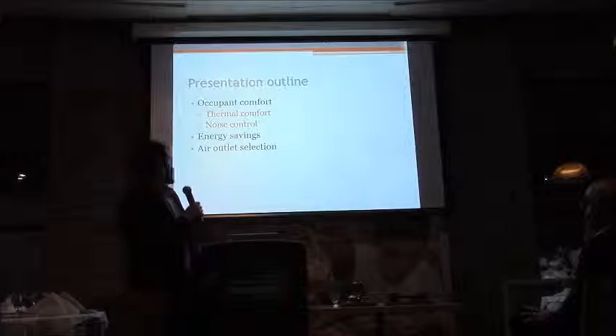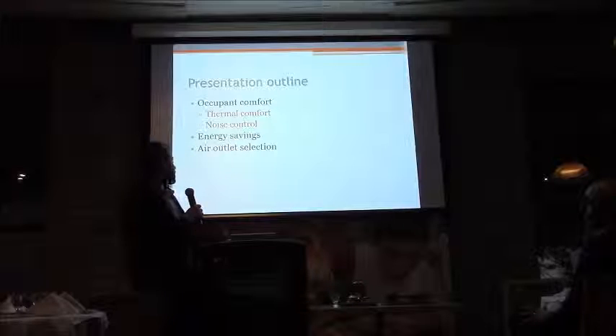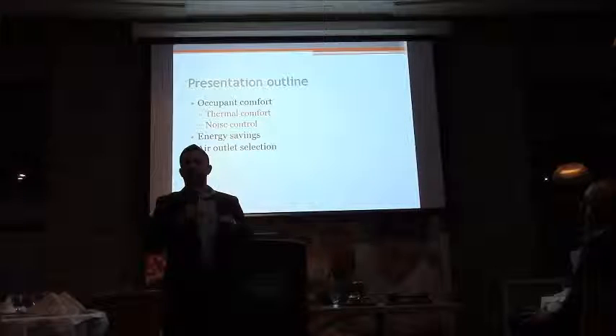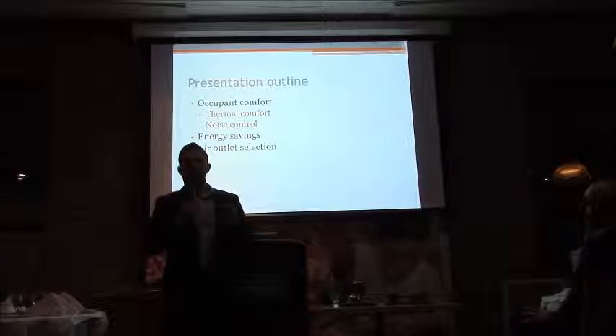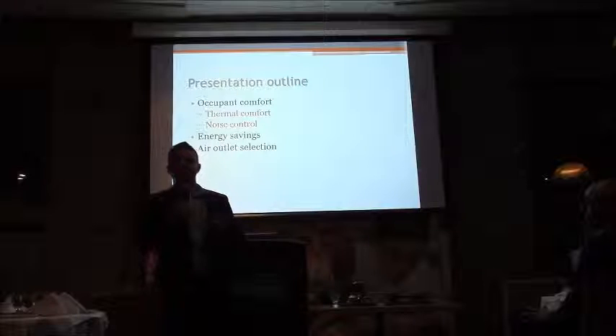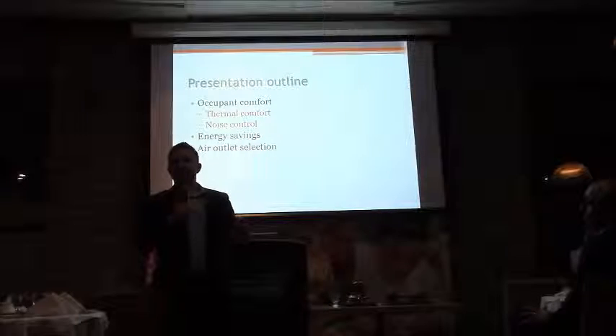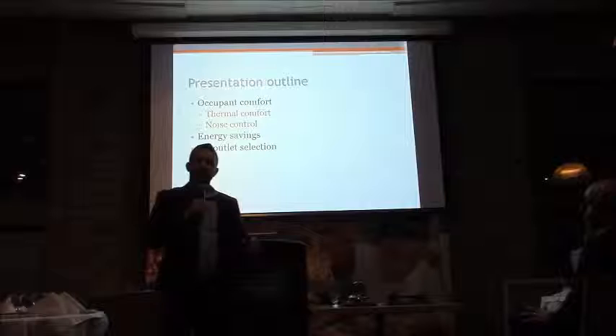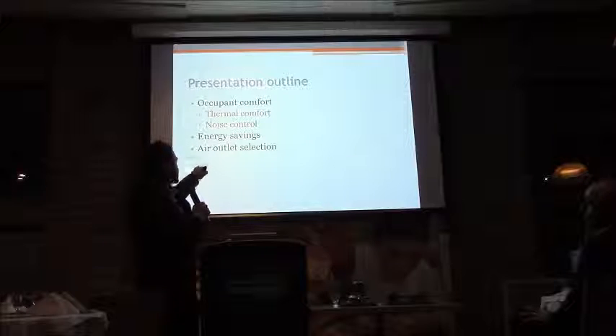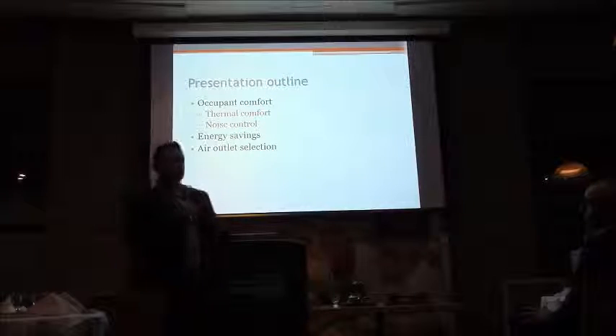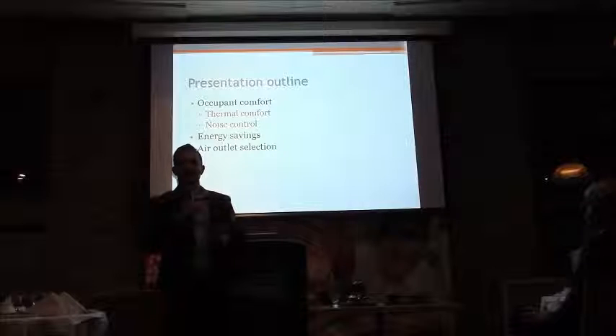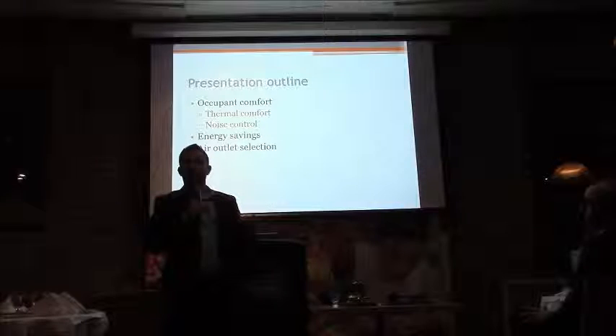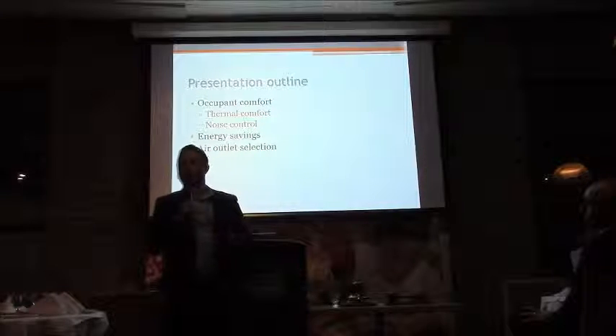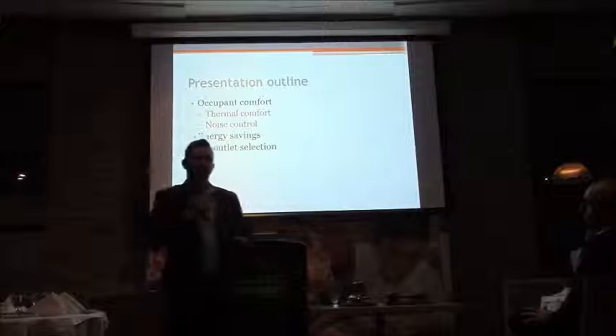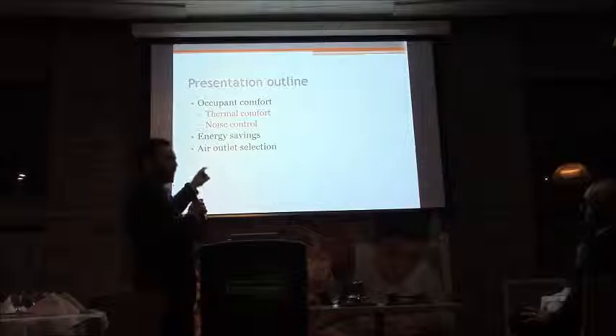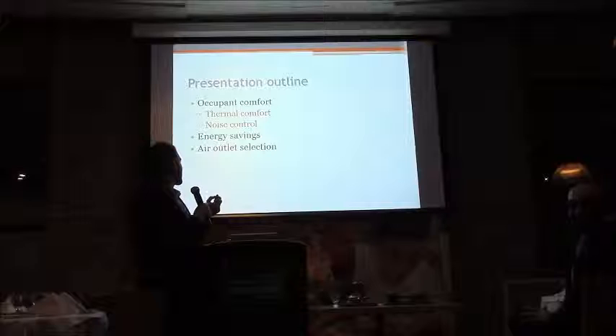So the outline of the presentation: we're not going to talk only about high induction diffusers as a product. It's really oriented on comfort, energy savings, and ASHRAE standards. And at the end of the presentation, we're going to do an air outlet selection. That's the only part where it's going to be product oriented. Because if I spoke about a diffuser for a full 1 hour, eventually I start losing part of the crowd. So it's really going to be on ASHRAE standards and comfort and everything.